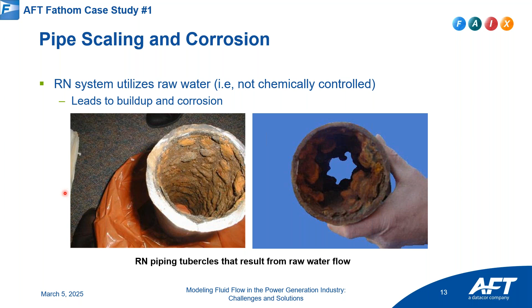And basically shrink the diameters to account for that, and then also change the pipe roughness according to measured pressures and flows. They didn't have pressures and flows for every pipe. They had just a certain number, about 20, around each of these different trains of operation. Data sets were provided from different operational configurations. So it wasn't just one measurement.